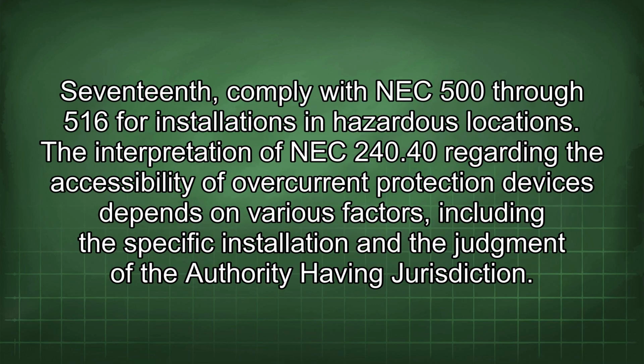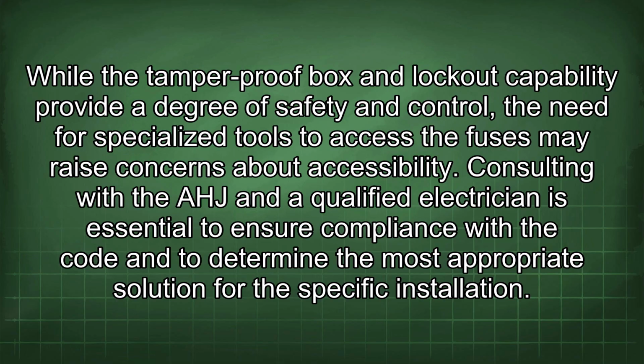17th. Comply with NEC 500 through 516 for installations in hazardous locations. The interpretation of NEC 240.40 regarding the accessibility of overcurrent protection devices depends on various factors, including the specific installation and the judgment of the authority having jurisdiction. While the tamper-proof box and lockout capability provide a degree of safety and control, the need for specialized tools to access the fuses may raise concerns about accessibility.